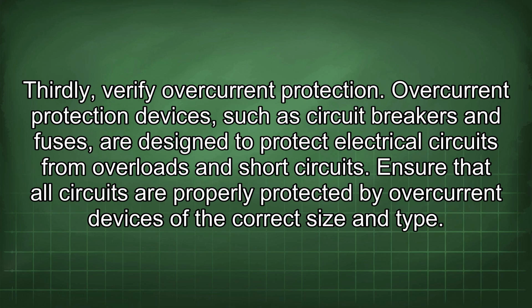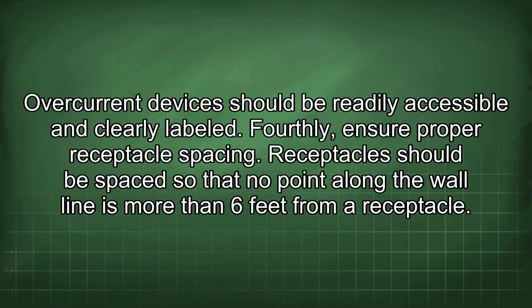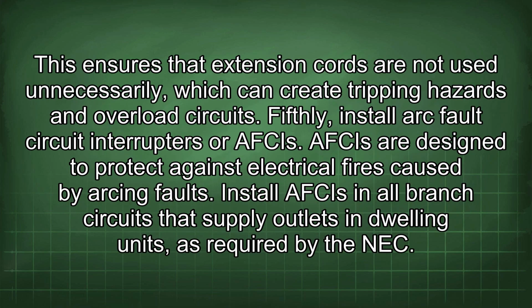Ensure that all circuits are properly protected by overcurrent devices of the correct size and type. Overcurrent devices should be readily accessible and clearly labeled. Fourthly, ensure proper receptacle spacing. Receptacles should be spaced so that no point along the wall line is more than 6 feet from a receptacle. This ensures that extension cords are not used unnecessarily, which can create tripping hazards and overload circuits.